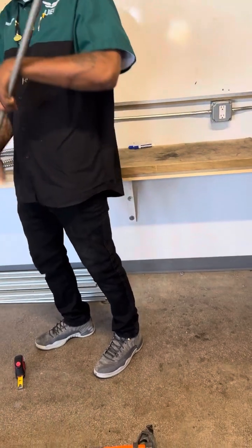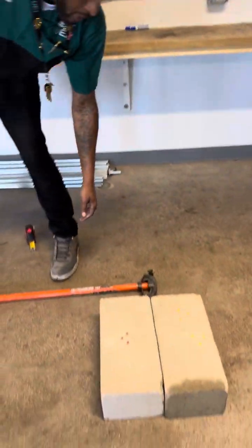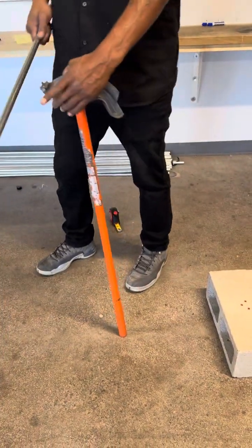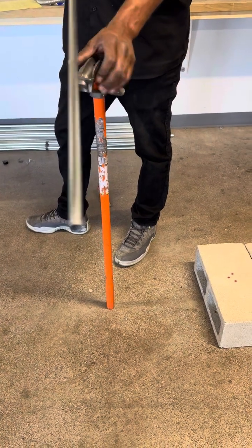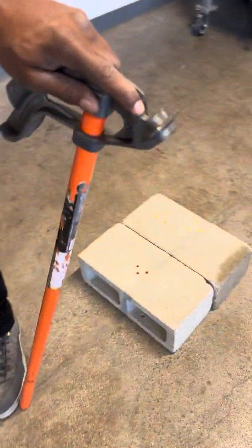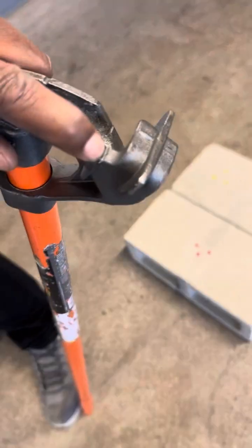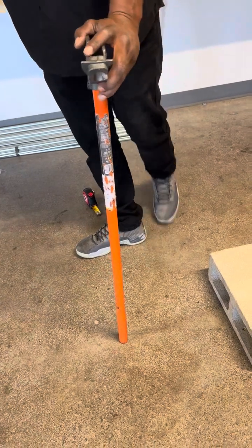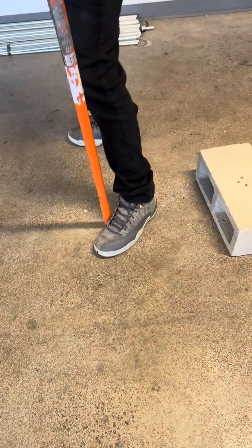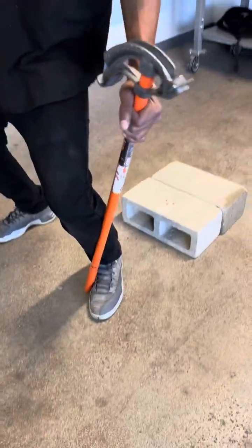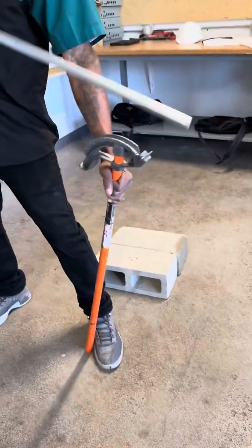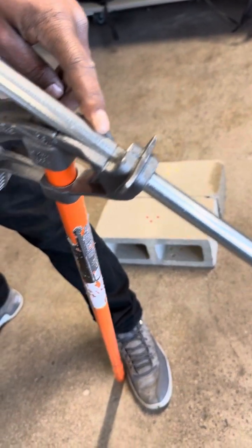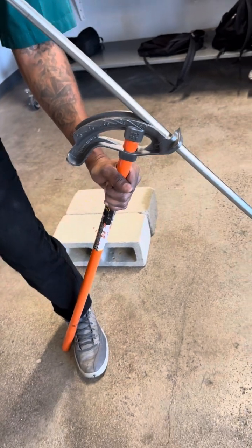There's 2 ways you can use this hand bender. For one, you can bend it up top, or you can use foot pressure to do it on the ground. But since this is a 1/2 inch pipe, I'm gonna do it from up top, okay? So my mark here is the first mark. I'll line it up with this mark here, with this arrow, as you can see. And now the first steps is always to make sure that you got proper control of the hand bender. So I teach my students to put their feet in here, knee bent, and now the pipe bender is in a wedge position and you can't slip it, as you can see. I insert my pipe, I line it up with this mark here, okay? I lock it in, and I'll take it down to 30 degree.